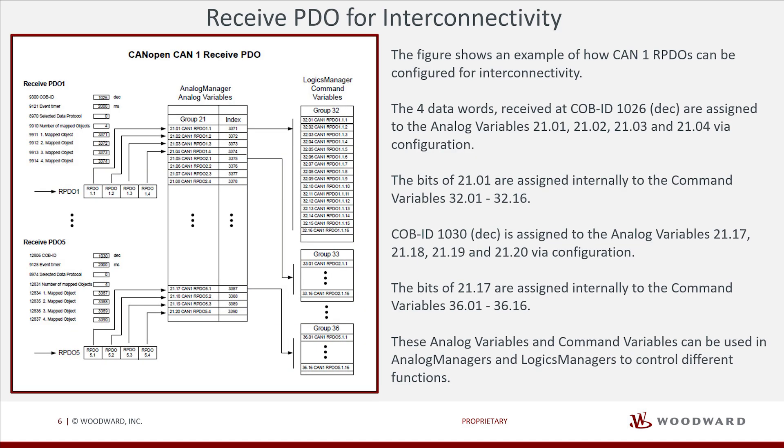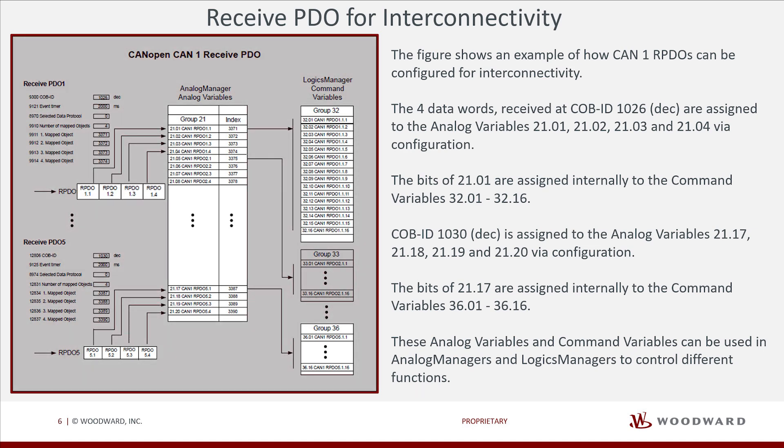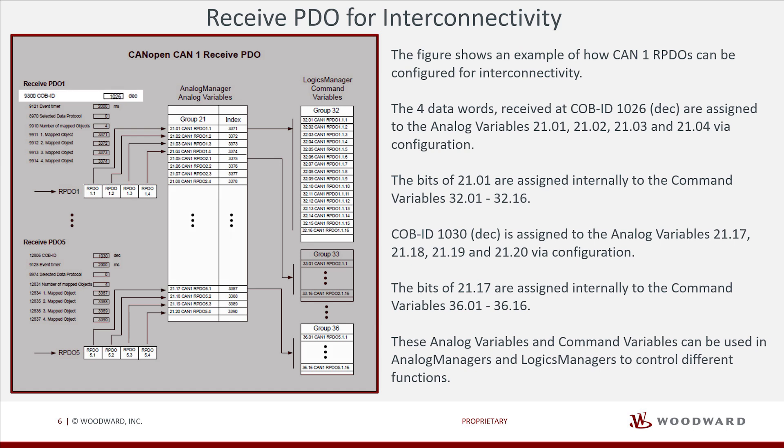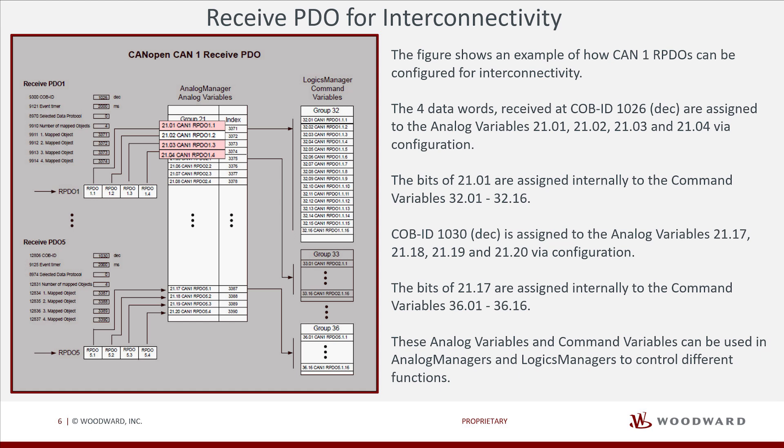Here is the example of how to configure the received PDO for interconnectivity. The four data words received at COB ID 1026 DEC are assigned to the analog variables 21.01, 21.02, 21.03 and 21.04 via configuration.